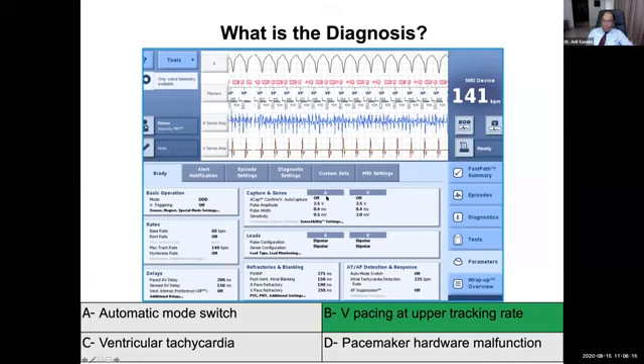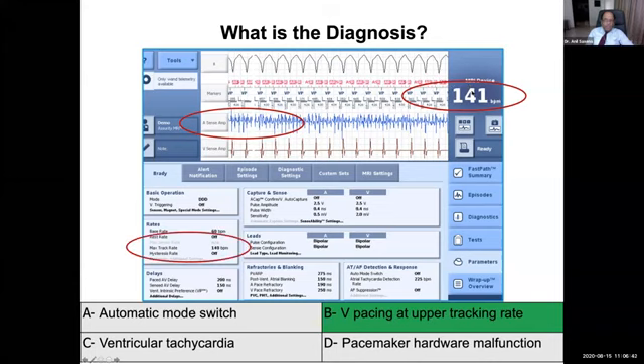The correct answer is V pacing at upper tracking rate, because if we focus our attention on the atrial channel, we can see that the patient is in atrial fibrillation. We can see the fast irregular atrial rate, and the ventricular rate is obviously slower. There are two other points that we must pay attention to. One, beside the atrial channel, is that the pacemaker is pacing at about 141, which is the same as the maximum tracking rate. So this is the important point. We must see what the upper tracking rate is and what the pacing rate is.